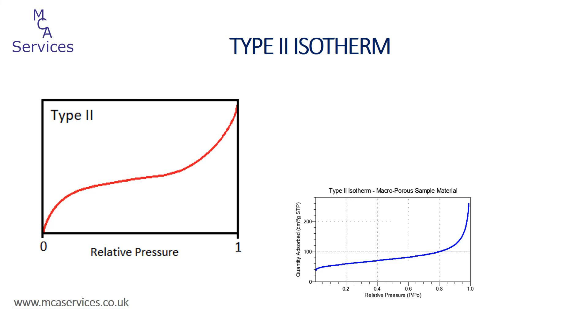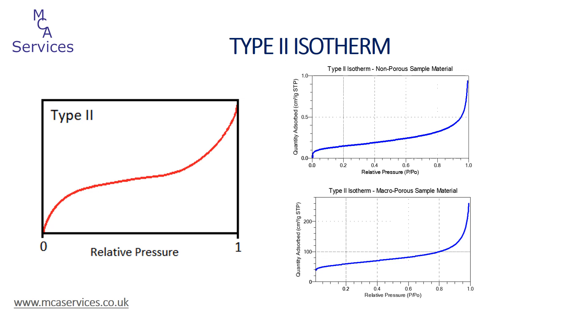There are two possible causes for this increase in adsorption volume. The first is multi-layer adsorption of adsorbate on adsorbate on the surface of a non-porous material, shown in the isotherm on the top right. The second is due to incomplete filling of pores in the sample. In the case of nitrogen adsorption at 77 Kelvin, macropores larger than about 200 to 300 nanometers in diameter are too large to be completely filled as saturation is approached. Consequently we see this asymptotic increase in adsorption volume.